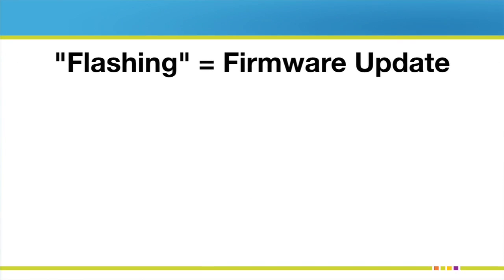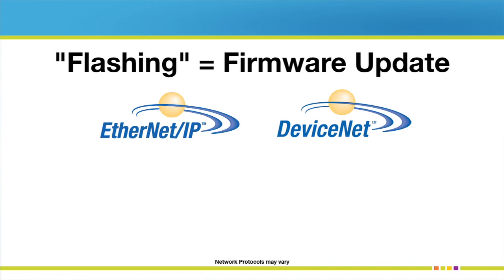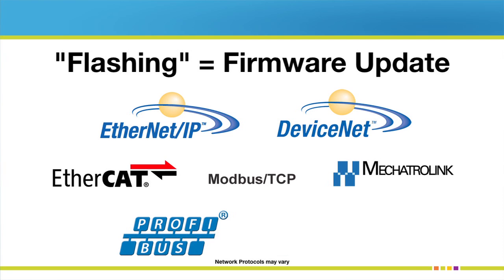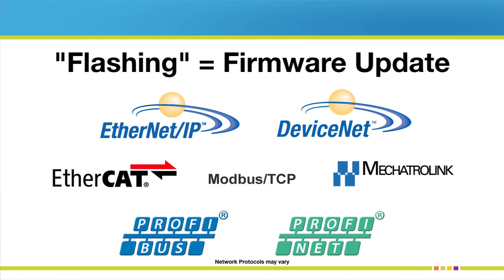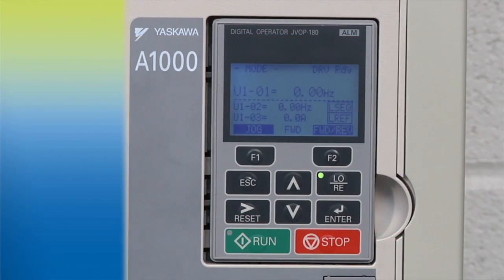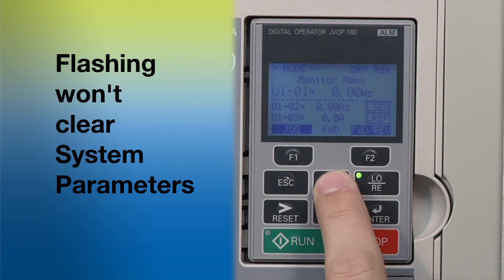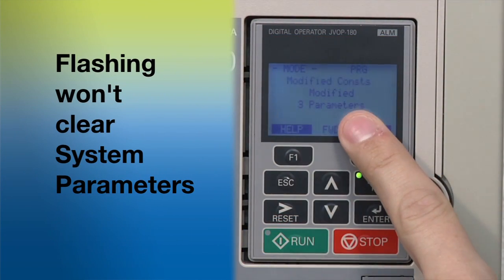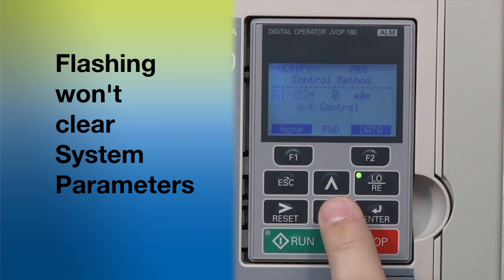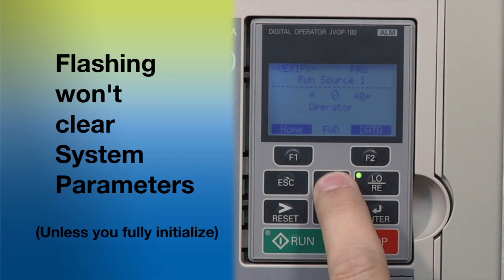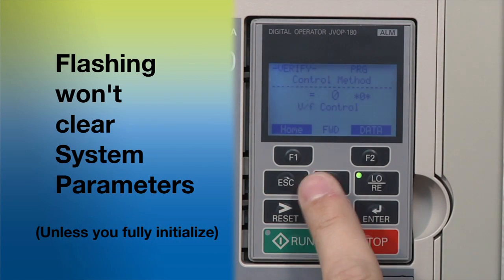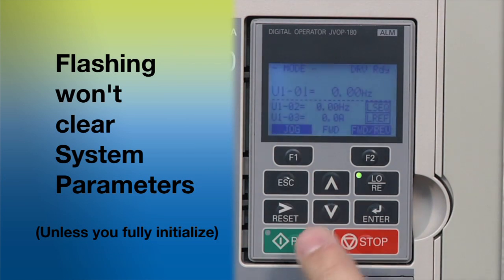Flashing keeps your software up to date with the latest fixes. In some cases, it can also add the ability to connect with the latest versions of common networking protocols. It is important to note that flashing won't clear out the system's current programming. You won't need to set up the drive's parameters or its operating functions all over again, unless you go beyond flashing to fully initializing the drive. And that isn't likely, because you don't commonly need to initialize when you flash a drive.